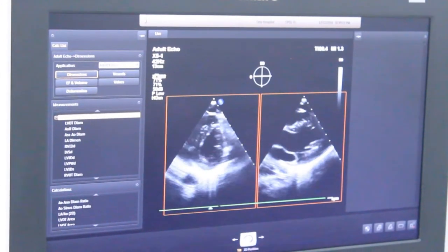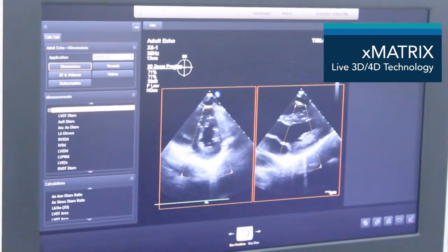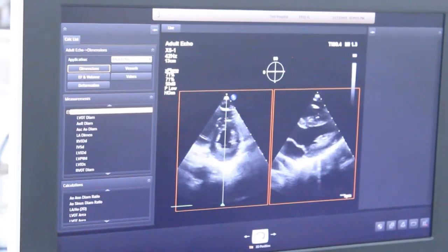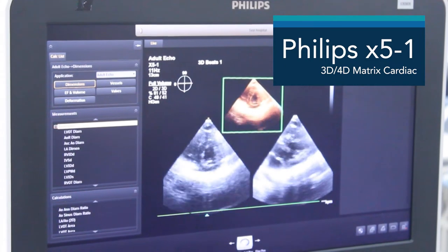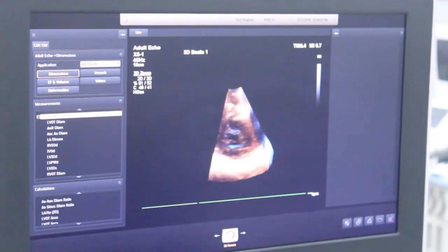In lieu of HDLive, the Philips EPIQ 7 runs Philips XMatrix, which is their live 4D cardiac imaging software. You can see that on the screen above with the Philips x5-1. It also runs the Philips X7-2, X7-2t, and X8-2t transesophageal probes. Notice the detail that XMatrix provides in this adult cardiac exam.